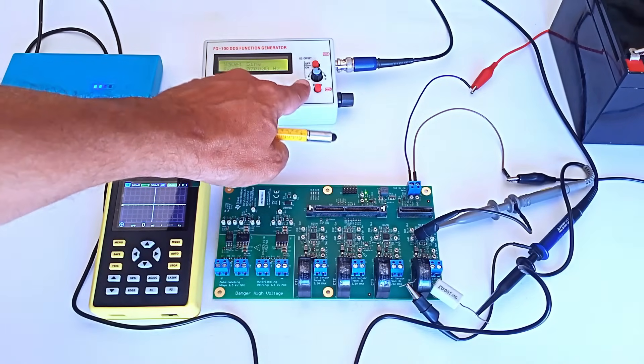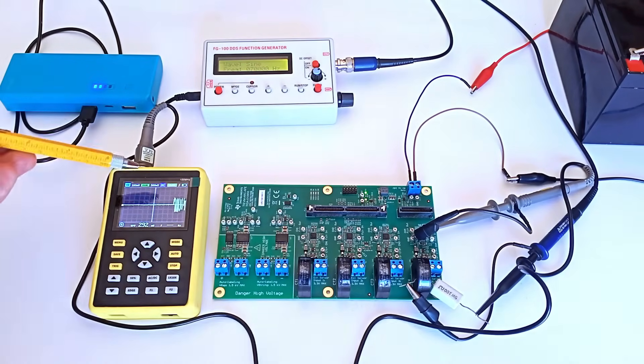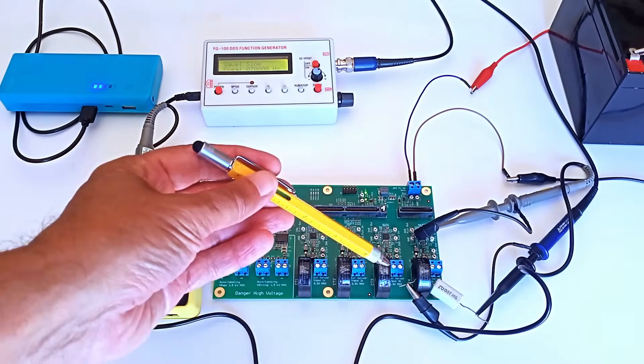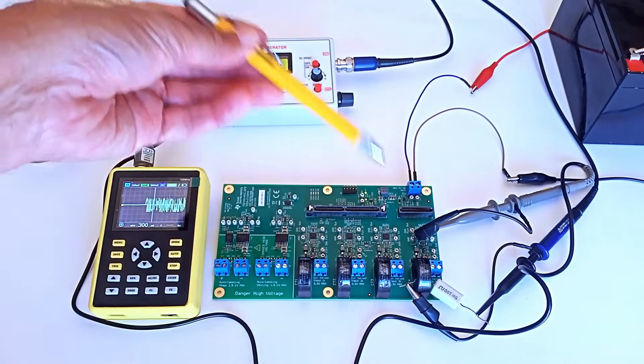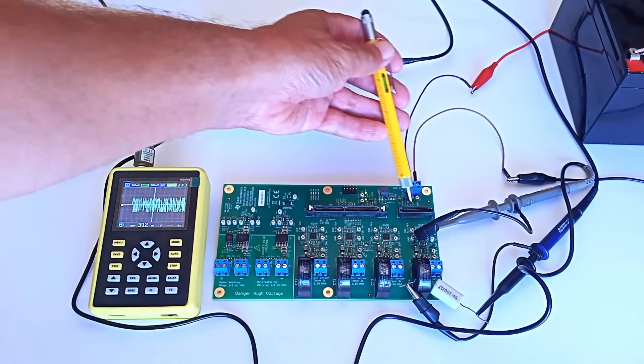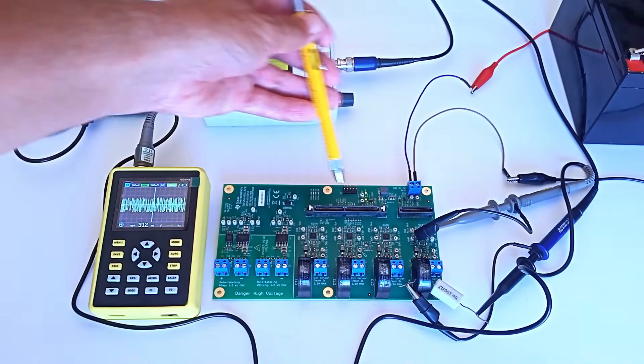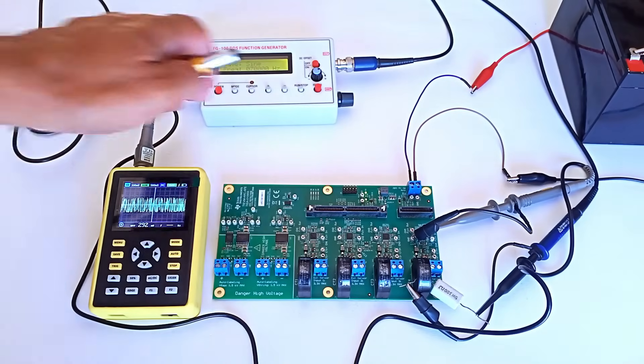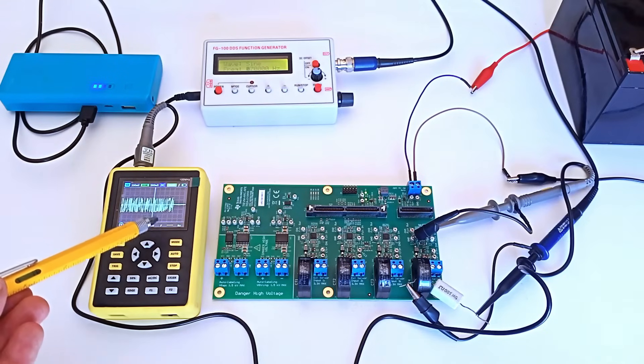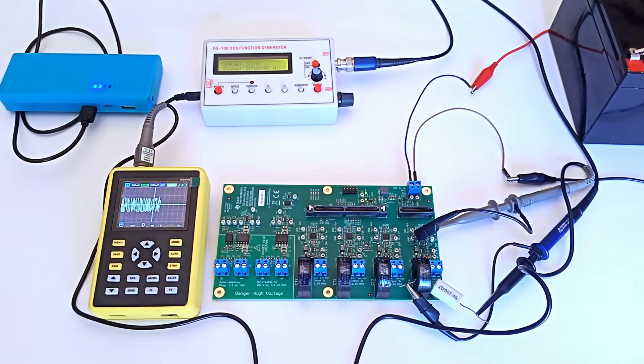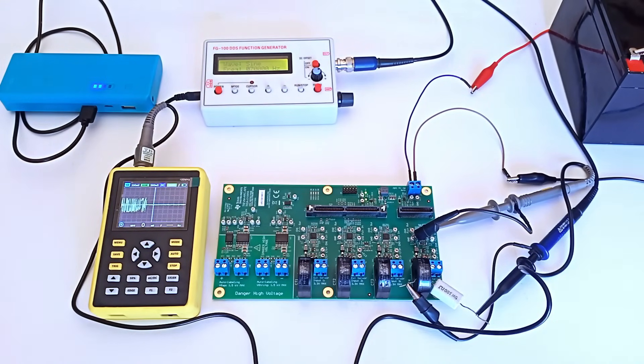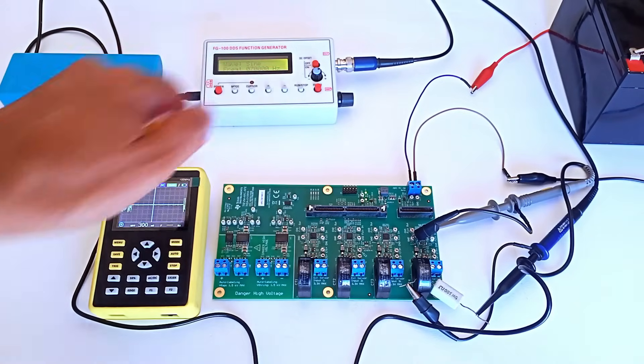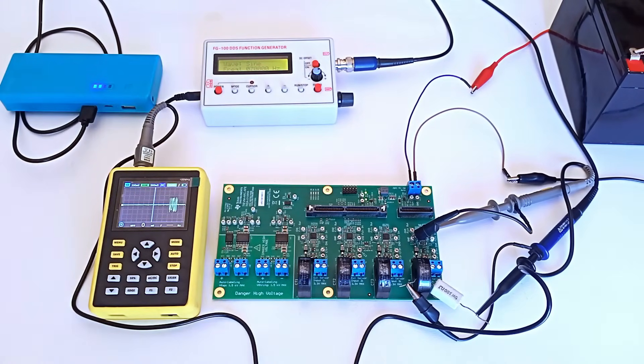As soon as the arc is generated, the signal appears at the output ready to be used by the AI board. When the arc signal is stopped, the measurement returns to zero. We re-simulate a short arc and the indicator signal reappears.